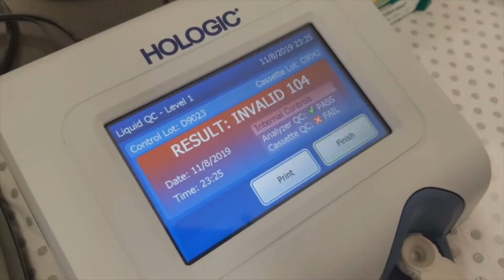Some of the issues that could occur include obtaining an invalid result. This will identify the problem with a code which is elaborated in the Hologic system manual. The possible failure for the cassette QC is dispensing less than 200 microliters of the control. In this case, repeat the control test on a new cassette and ensure the correct procedure is followed.